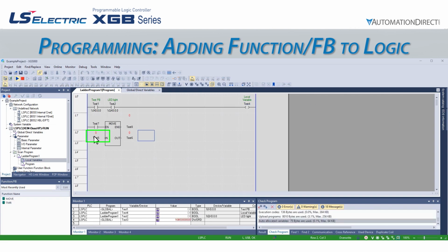If we download this to the CPU and place it into run mode and monitor mode, we can set test5 to true, and test6 remains false. If we make test7 true to enable the move function, we see that the test5 state has been moved into test6, and test8 became true, indicating that the function was enabled. If we make test7 false, we see test8 go false as well. We can then make test5 false without influencing the state of test6, as the move function is no longer enabled.